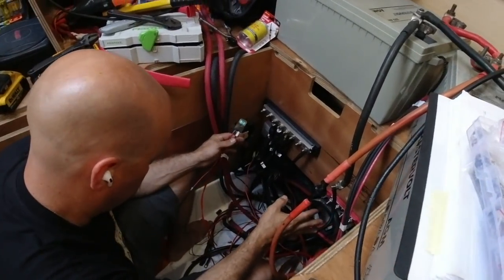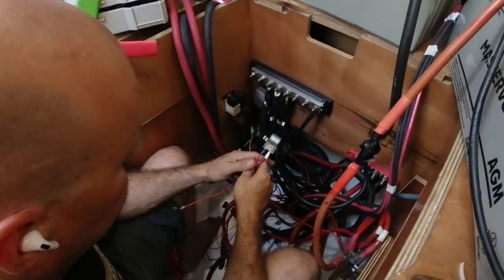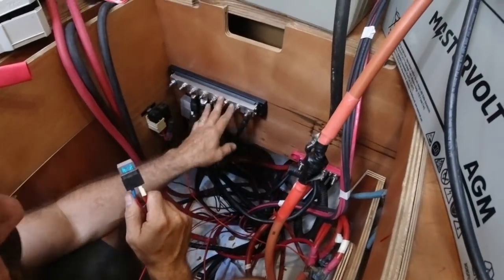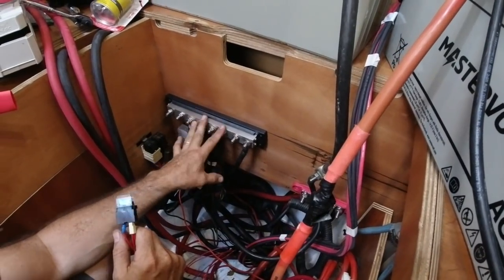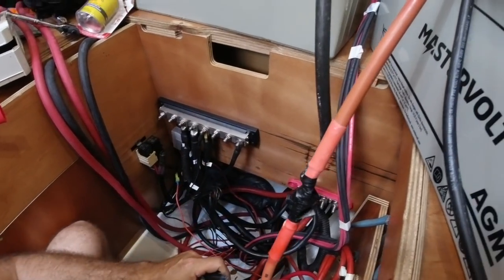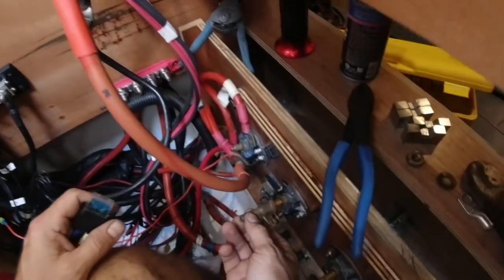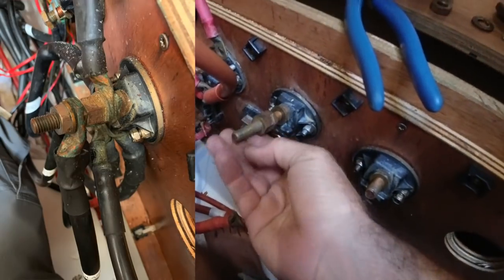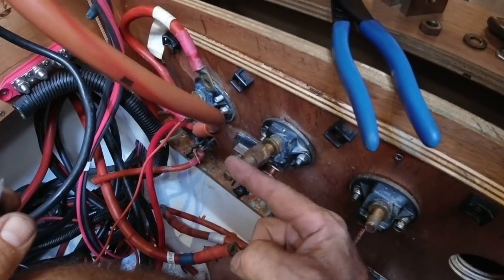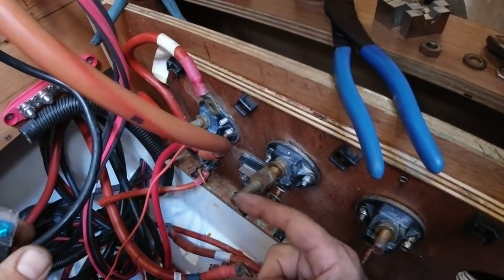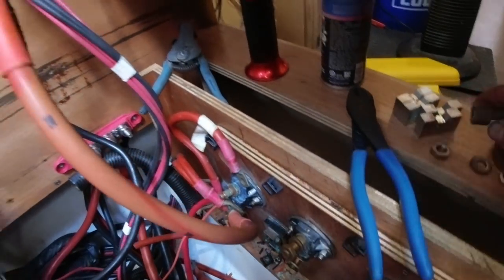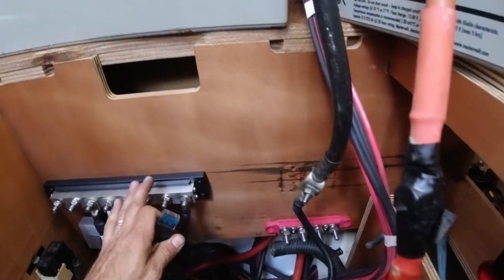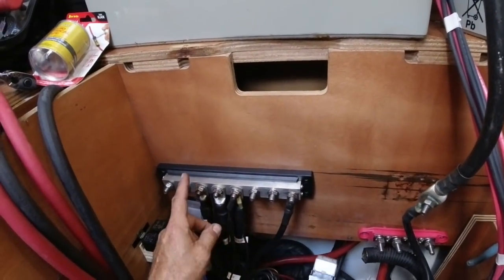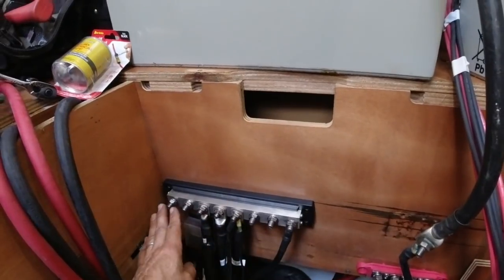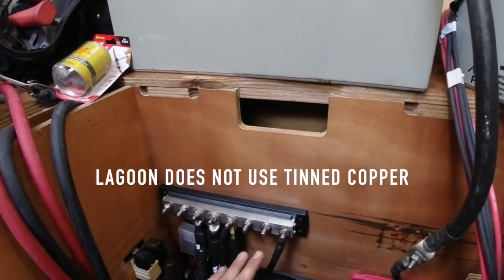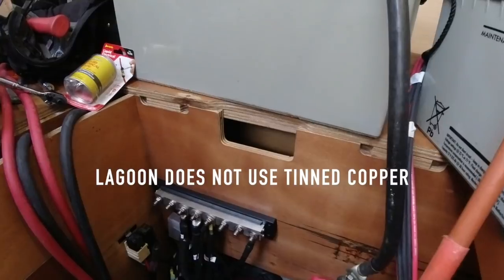So there's actually a method to this madness down here. It looks like a mess, but I know there is a method. All of these were bolted down to one of these posts on either side with these goofy extensions screwed on, with stacks and stacks and stacks of ground wires. So we took all of this off and we're moving everything to a bus bar, cleaning everything up, putting all new connections on. Anything that has any level of corrosion, we're taking care of.